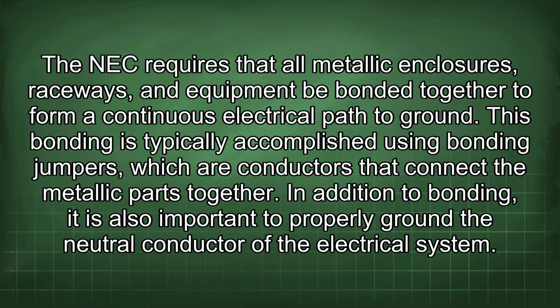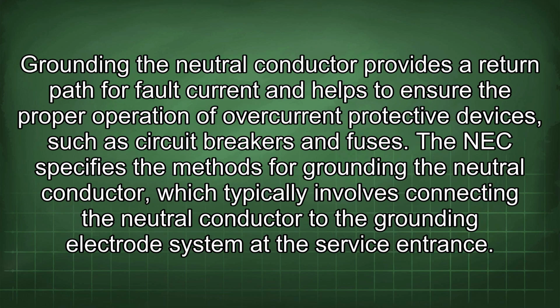In addition to bonding, it is also important to properly ground the neutral conductor of the electrical system. Grounding the neutral conductor provides a return path for fault current and helps to ensure the proper operation of overcurrent protective devices, such as circuit breakers and fuses. The NEC specifies the methods for grounding the neutral conductor, which typically involves connecting the neutral conductor to the grounding electrode system at the service entrance.